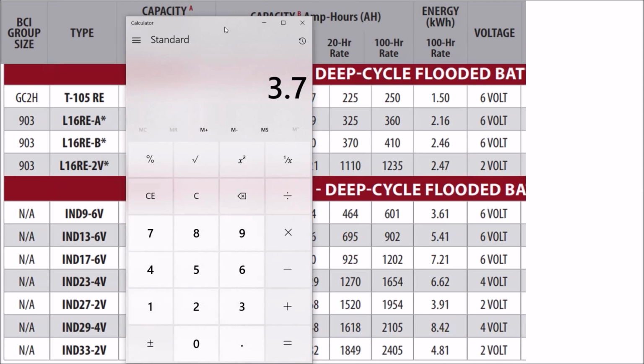Now, I can only have 2 circuits of these because when you get into multiple battery circuits you get that degradation issue from different conductor lengths. So if I have a 2-volt battery — most battery inverters are 48 volts, though lithium-ion-specific inverters like Tesla's may operate at a higher voltage — but your Outback, Schneider, SMA are all 48-volt battery inverters. So you divide 48 volts by 2, meaning the maximum batteries per circuit, if we're using 2-volt batteries, is 24.